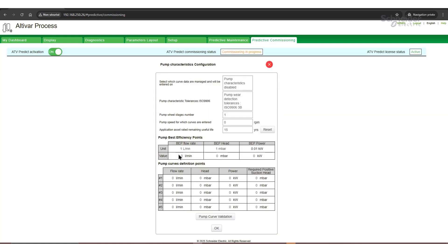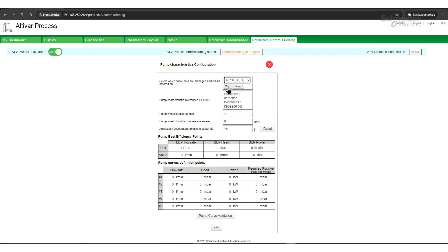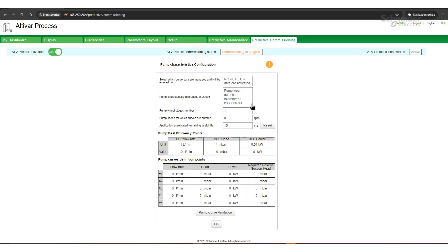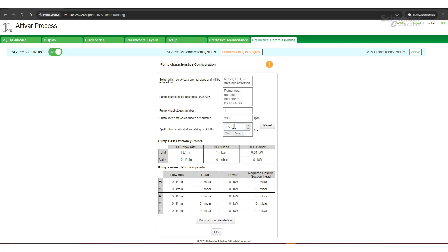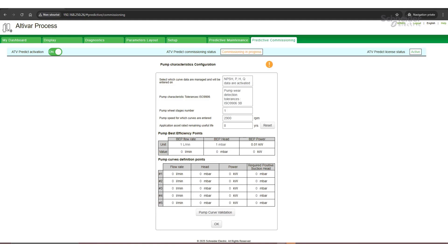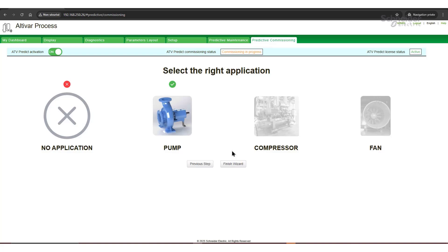Now we can configure the pump. Depending on the available information, we can select which curve data is managed and will be entered. We select net positive suction head, pressure, and flow data to be activated. Pump wheel stages number is 1. Pump speed for which curves are entered is 2900 revolutions per minute. We can adjust the application's asset rated remaining useful time — let's set it to 8 years. Next, we need to enter the pump curve point by point; in this video, we don't show these actions and proceed to the validation. When clicking on pump curve's validation, we can see that the status indicator turns green. Now we can see that the status of all parts is green. We can click Next Step and exit the wizard.